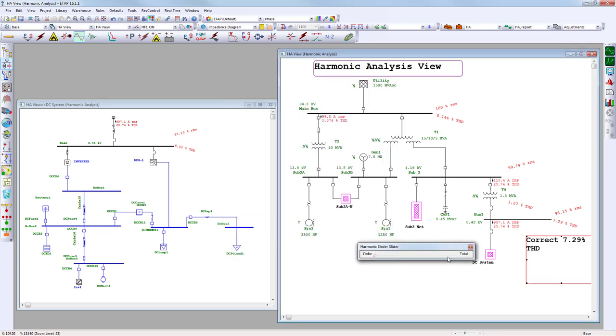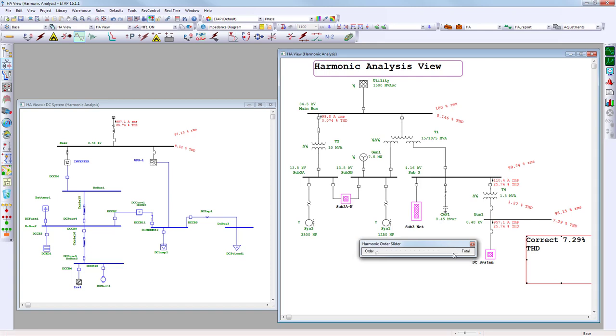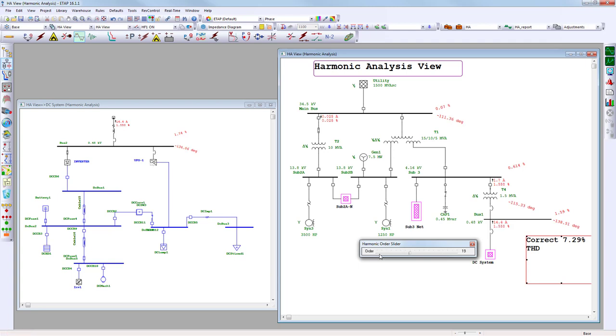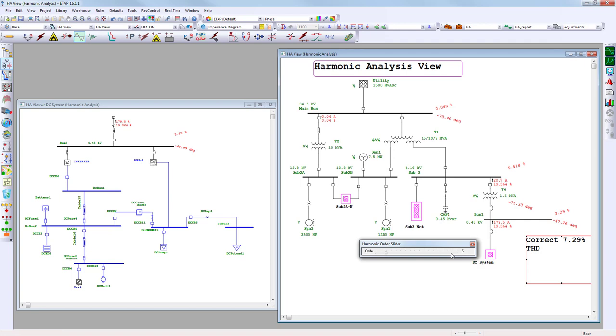The harmonic order slider is a very useful tool. As you scroll to the right you have the fundamental frequency — basically your steady-state load flow results — and then scrolling further you see your 5th, 7th, 11th, 13th harmonics and so on. You can specify how far to go in the study case. Since this is a six-pulse drive, there is predominant harmonic content on the 5th. At bus one, the 5th order is 179.5 amps, 124 amps on the 7th, and 71.6 amps on the 11th.